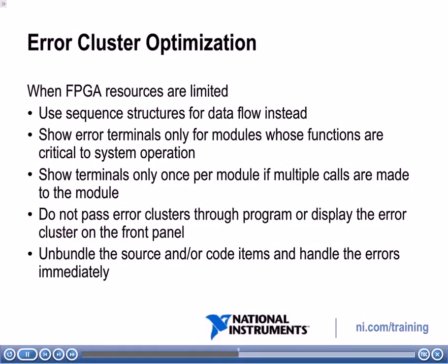error in your program. Also, if you have an IO module in multiple places and you only want to check on some of the general errors associated with that particular IO module, then show the terminals only once for that module, and you can periodically check the errors on that module instead of showing the error terminals on every instance of that IO module.